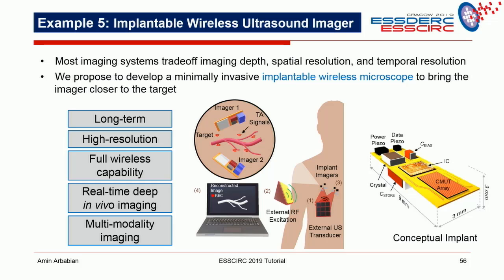So the specs we set out here, I have the block diagram of the system looking in the center. So this is a thermoacoustic imaging system. It consists of 2 parts. One is stimulation. So you need a laser or an RF source that's pulsed that generates the stimulation. If you're familiar with photoacoustic, thermoacoustic is almost the same. It just uses an RF source. So that's external. External to the body, I have a laser source or an RF source that generates the stimulation. This is an RF pulse. It comes in to stimulate the tissue so we can receive the ultrasonic response.